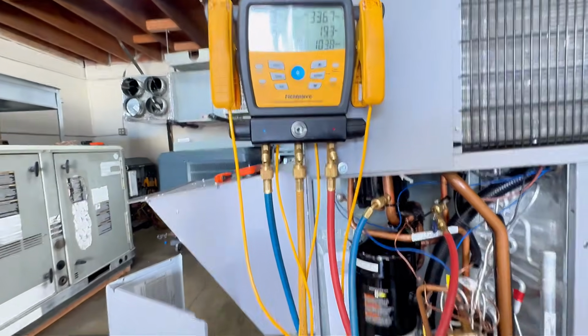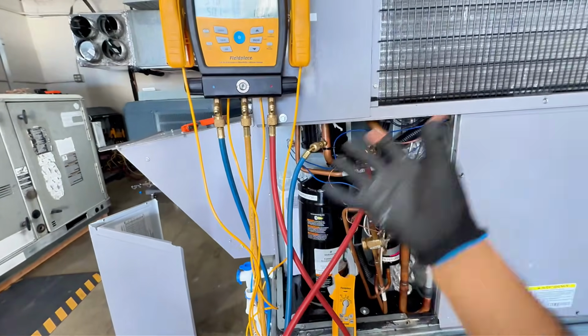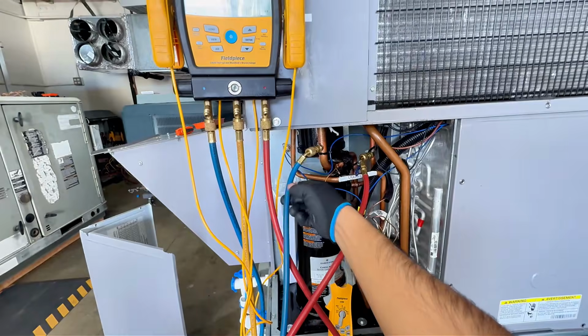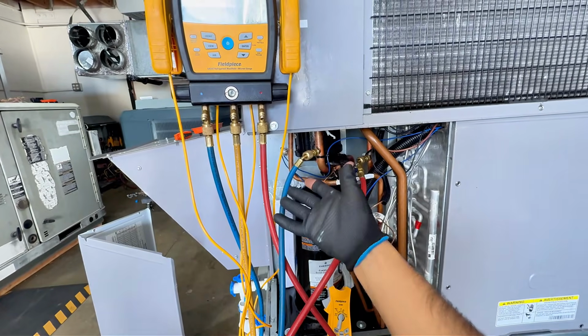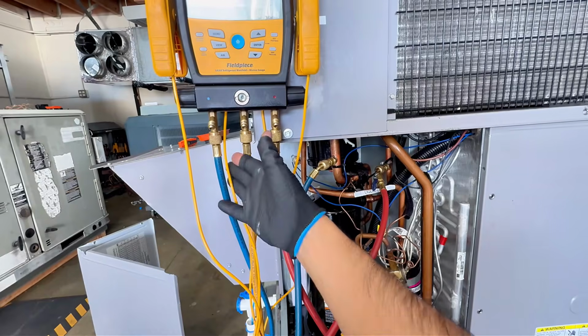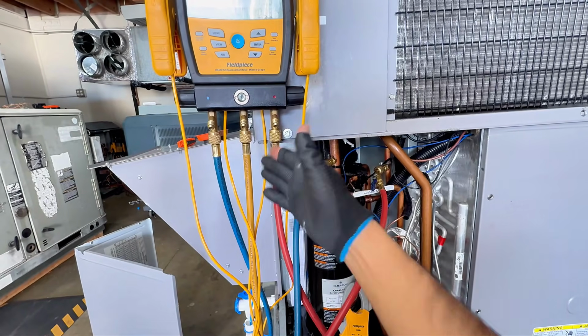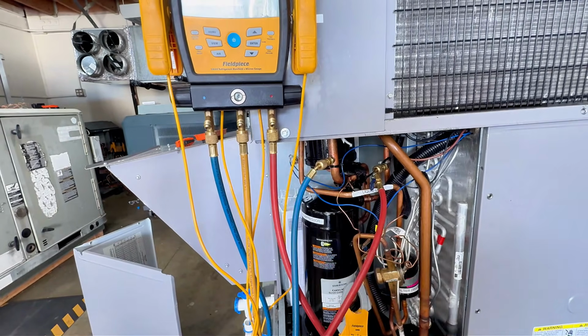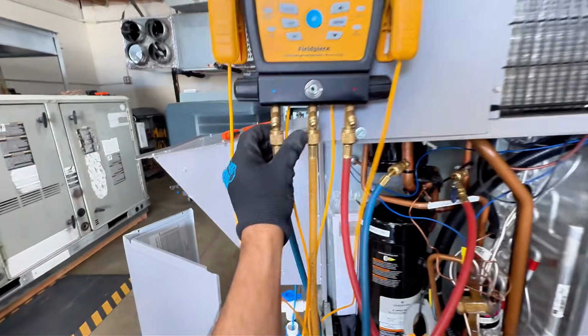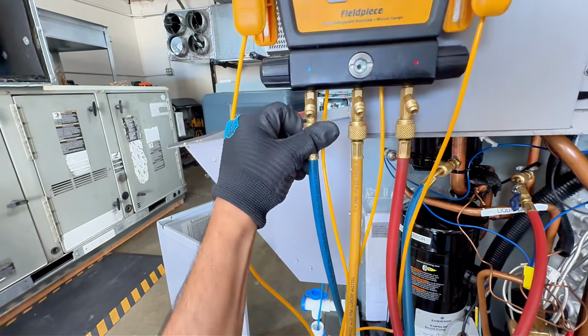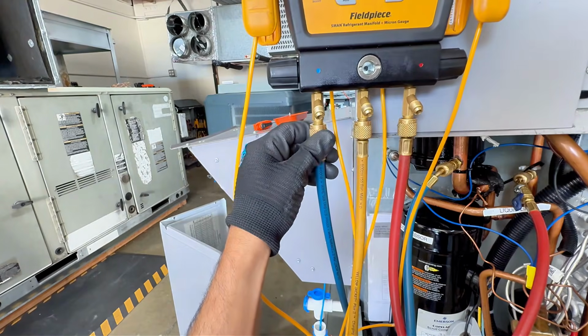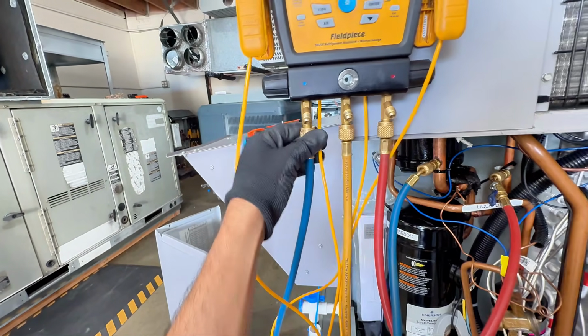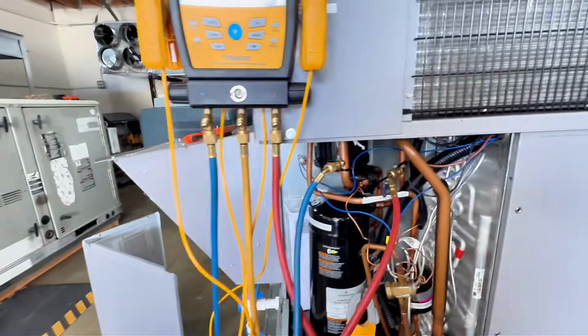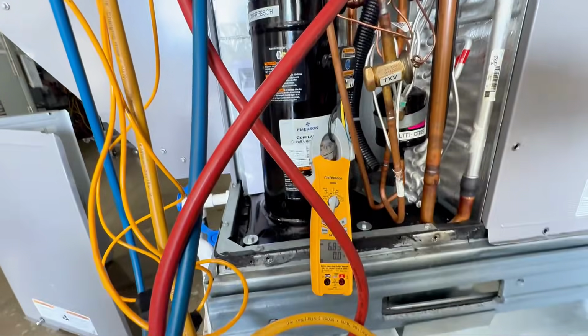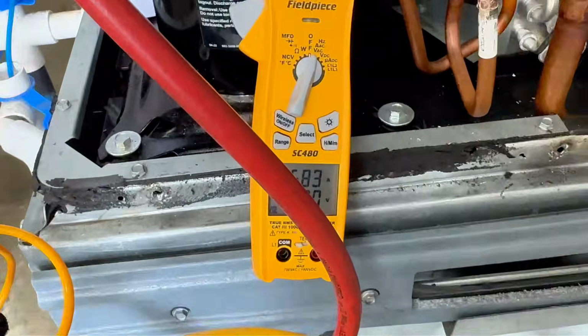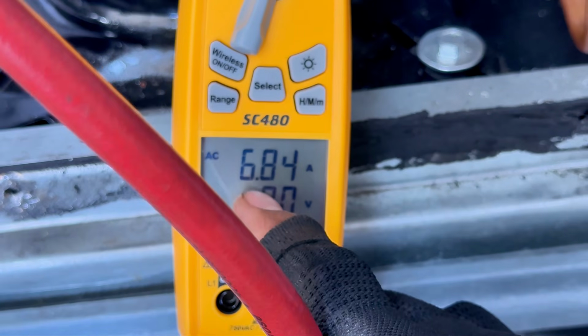A little pro tip here, because we're not pulling a vacuum, this blue line does have a little bit of air, and you're going to be charging on the blue side, because it has to go on the low side, since the higher pressure goes to lower pressure. So we have to charge on the low side. So what I like to do when I connect it, I like to just purge very little, get some air out of that hose. Now I have just refrigerant going in there. So now that we have everything set up, and it might take me a bit, but 6.8.